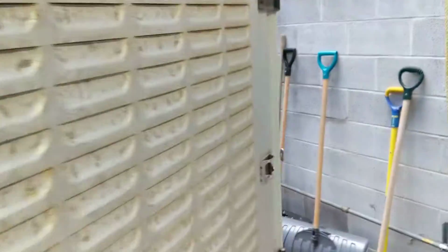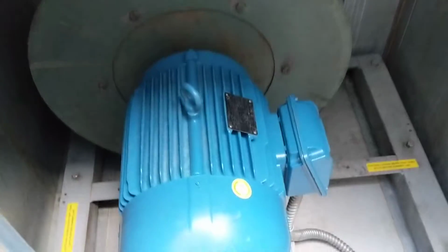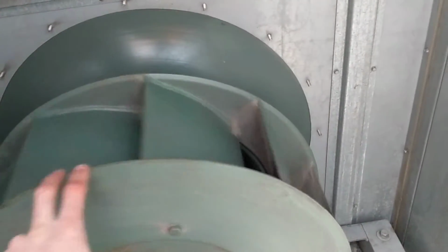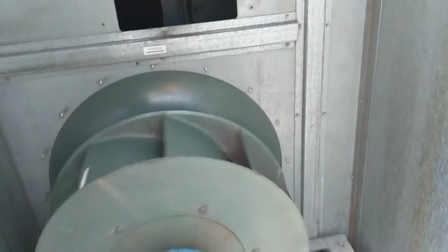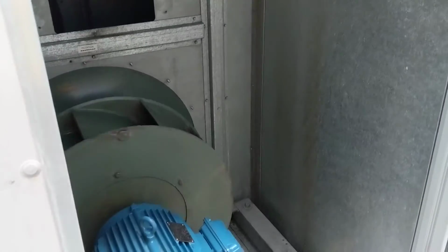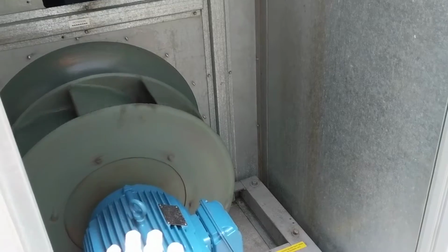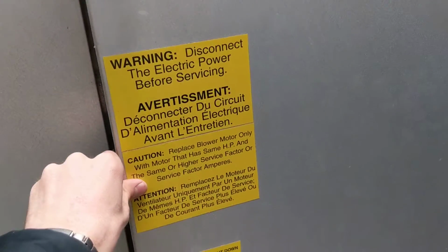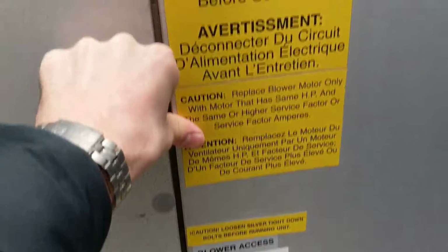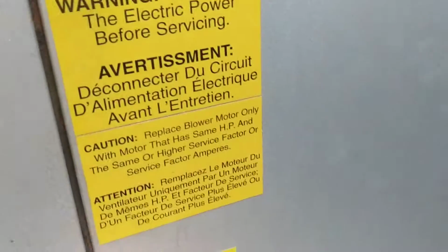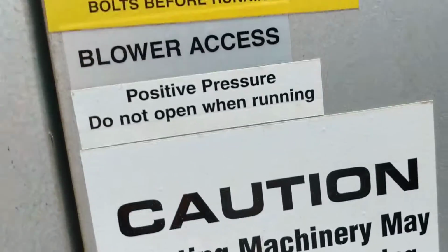And the motor that runs the air through the unit and through the arenas is over here. And so both of the motors in this were replaced recently, within the last 2 years. So this motor is brand new, and so is the one over there. This is what is moving the air through here. You never want to open this door with that running, because there's massive positive pressure there. And this wheel takes a long time to stop spinning after it's shut off. So you'll see here that it has warning labels to make sure that you disconnect before servicing and not to open due to the positive pressure.